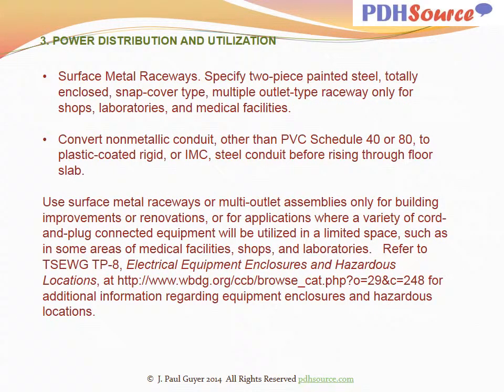Surface metal raceways: specify two-piece painted steel, totally enclosed, snap cover type, multiple outlet type raceway only for shops, laboratories, and medical facilities. Convert non-metallic conduit other than PVC Schedule 40 or 80 to plastic-coated rigid or IMC steel conduit before rising through floor slab.